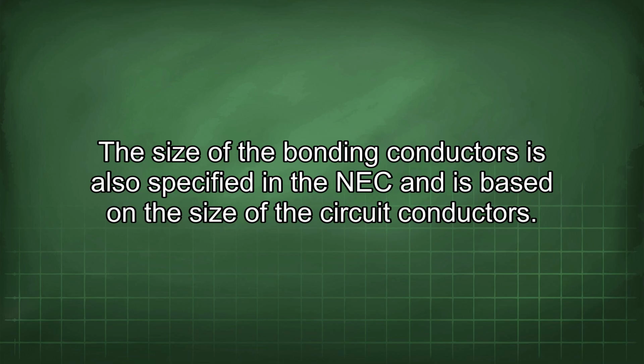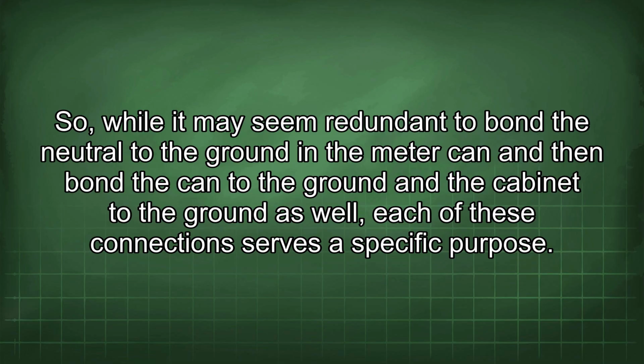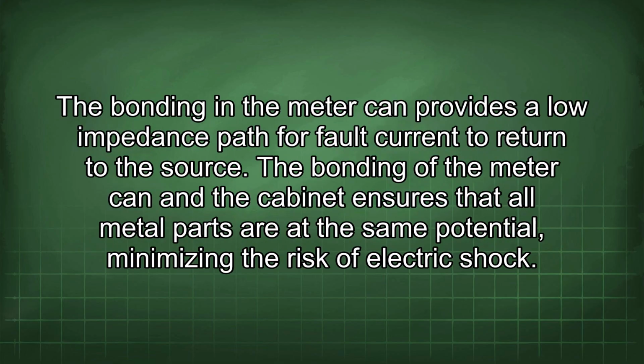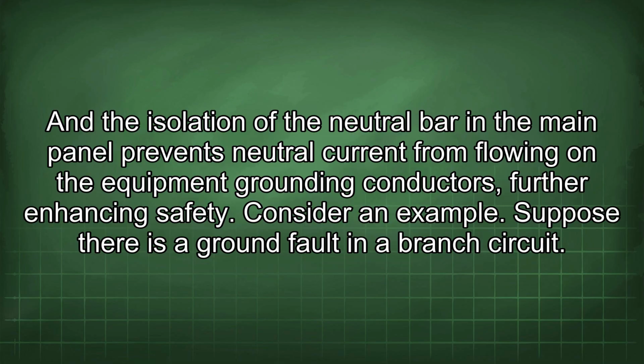circuit conductors. So, while it may seem redundant to bond the neutral to the ground in the meter can and then bond the can to the ground and the cabinet to the ground as well, each of these connections serves a specific purpose. The bonding in the meter can provides a low impedance path for fault current to return to the source. The bonding of the meter can and the cabinet ensures that all metal parts are at the same potential, minimizing the risk of electric shock. And the isolation of the neutral bar in the main panel prevents neutral current from flowing on the equipment grounding conductors, further enhancing safety. Consider an example.